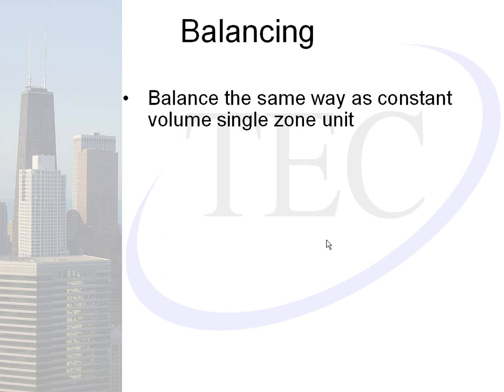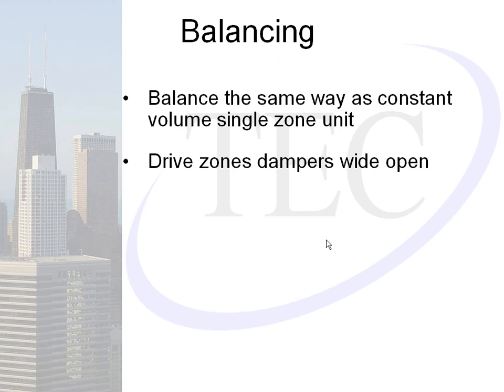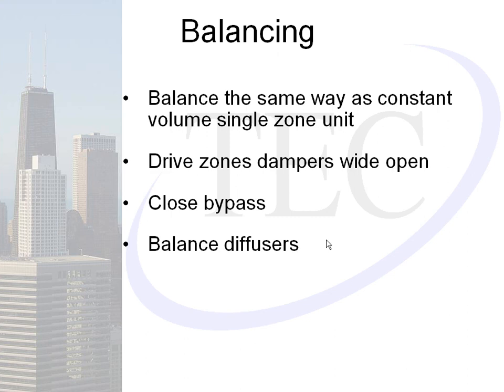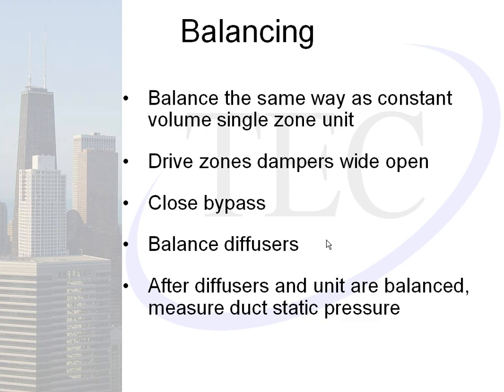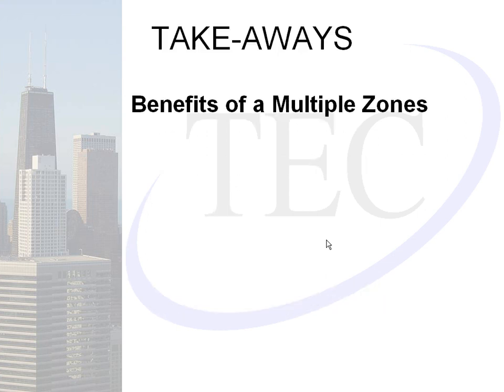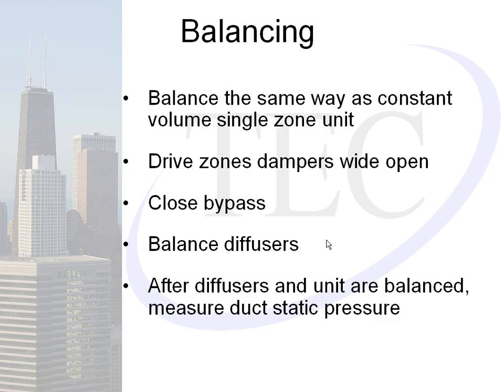Balancing a VVT system is actually very easy. VVT gets balanced the same way as a constant volume single-zone unit. Put the system into balancing mode, which drives all zone dampers wide open and closes the bypass damper. Balance your diffusers and rooftop according to design. After balancing, measure the duct static pressure — that becomes the static pressure set point for your VVT system residing in the bypass controller.